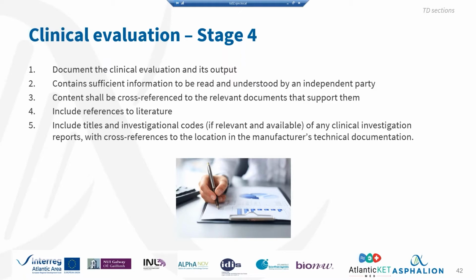Okay, you've got to make certain that this report contains sufficient information to be read and understood by an independent party. That means that you have to set a background to the medical device, a description of the device. It's not just including the clinical data within this report, and that's all. You've got to place a background so that anybody that reads the report can find out and can agree or disagree with your opinion on the fulfillment of the safety and performance requirements. So the content inside the report shall be cross-referenced to the relevant documents that support them.